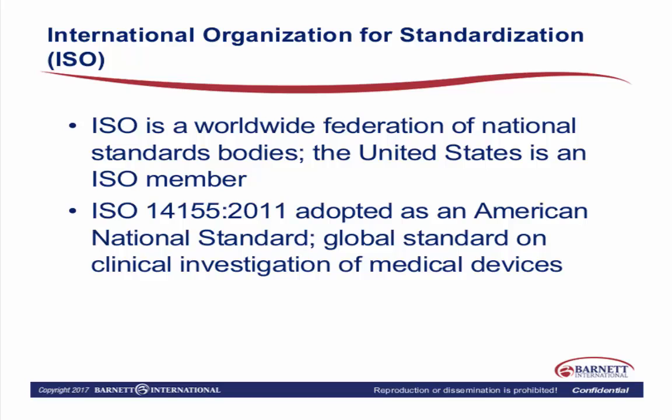ISO is a worldwide federation of national standards bodies — the U.S. is part of that, it's an ISO member. We adopted ISO 14155 in 2011. It was split into parts one and two prior to that and served for several years in that format, then consolidated and updated in 2011 and adopted as a global standard on clinical investigation of medical devices. We still see in protocols for IDE studies where folks follow 21 CFR 812 and layer in ICH E6 as well as ISO — they're complementary.